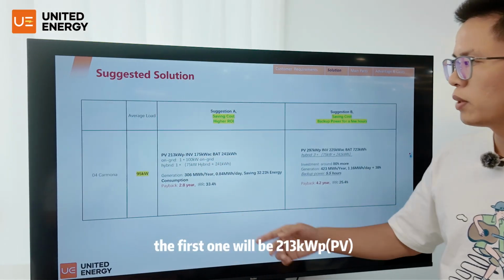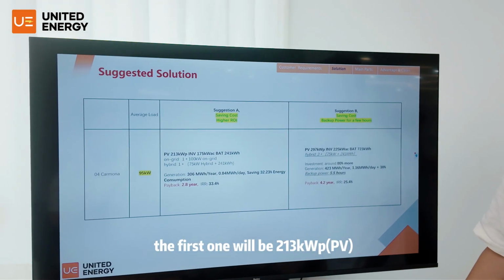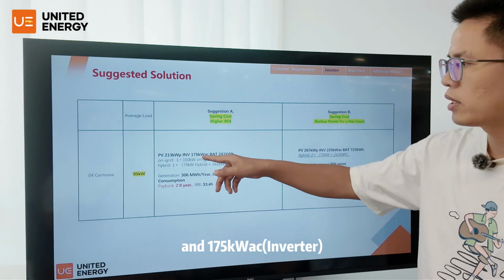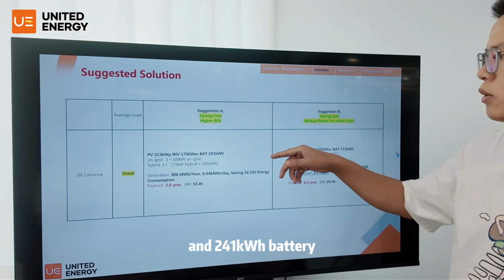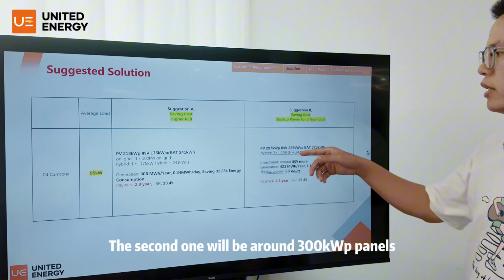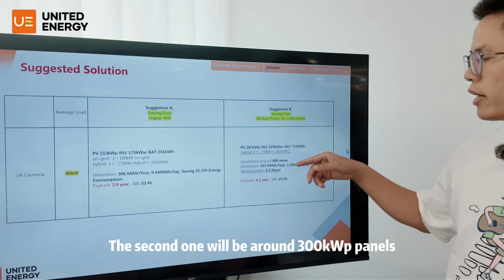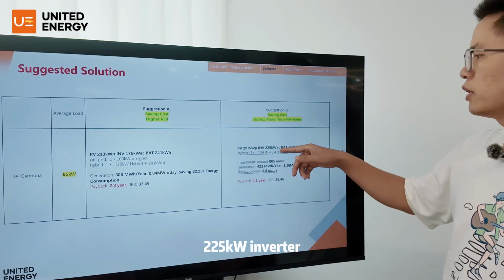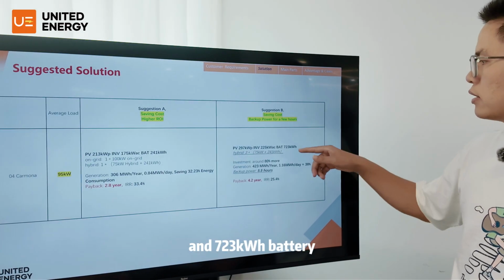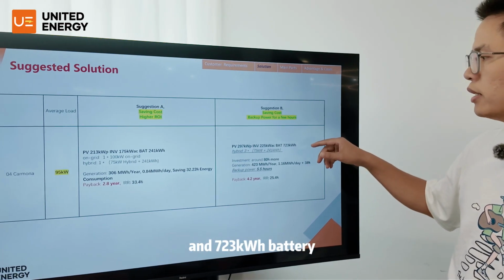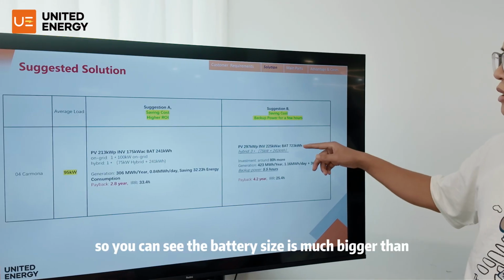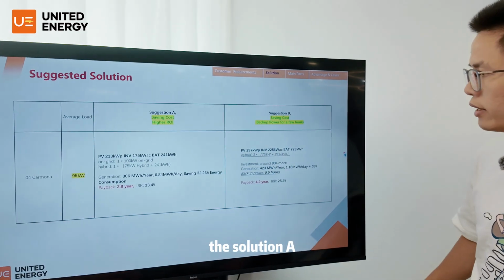The first one will be 213 kilowatt peak, a 175 kilowatt inverter and a 241 kilowatt hour battery. And the second one will be around 300 kilowatt peak panels, a 225 kilowatt inverter and a 700 kilowatt hour battery. So you can see the battery size is much bigger than solution A.